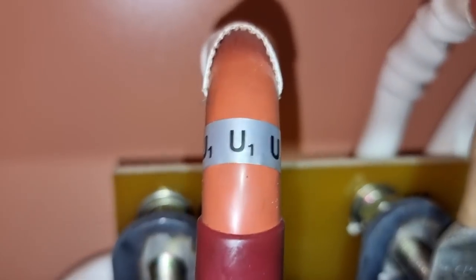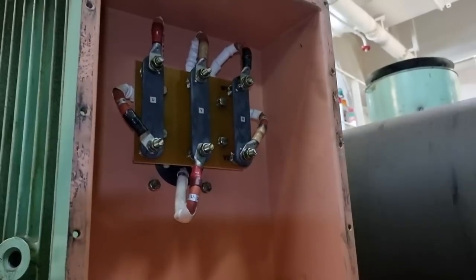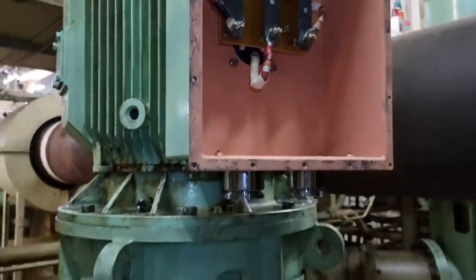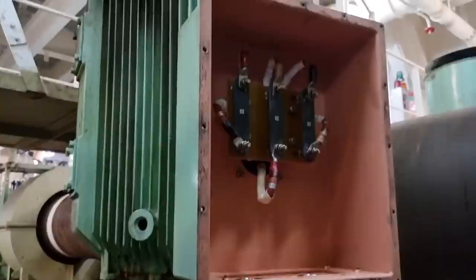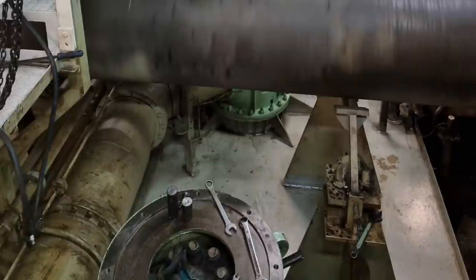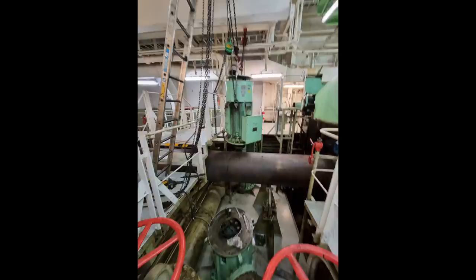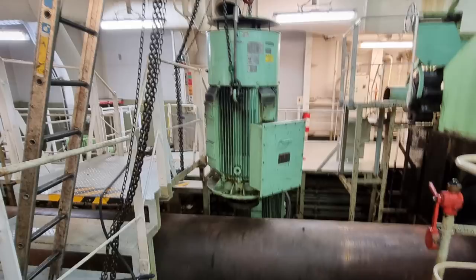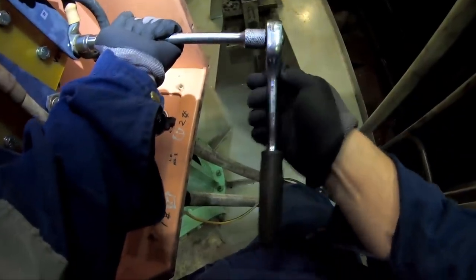After taking all those measurements, I found out that the windings of the motor is still in good condition and it is not grounded. I've decided to remove the power cables all the way because they are going to lift the motor. This is already the second engineer's job. They check the pump and change the coupling and finally they replace some parts of it. After fixing all these mechanical troubles, then they asked me to put back all the cablings. Please make sure to use this shrinkable tube to insulate the gland properly.